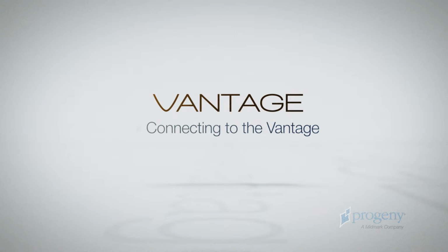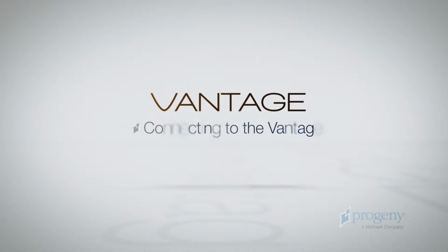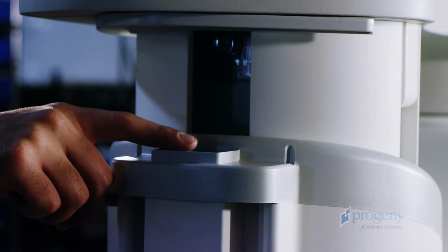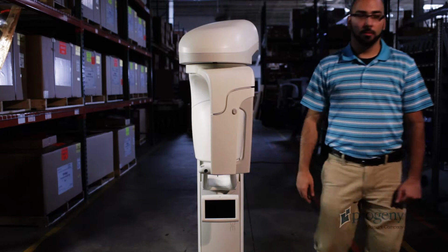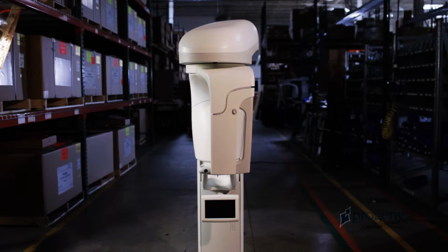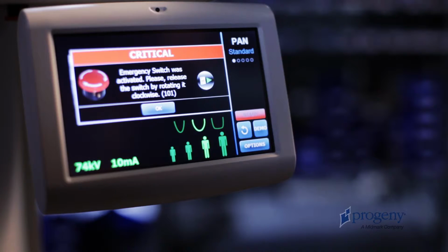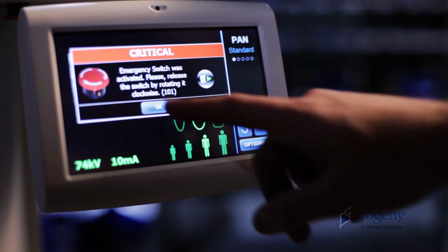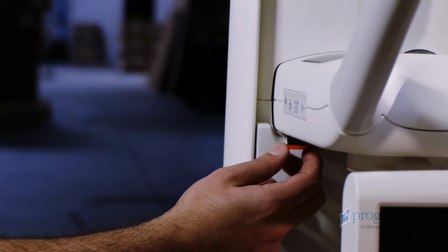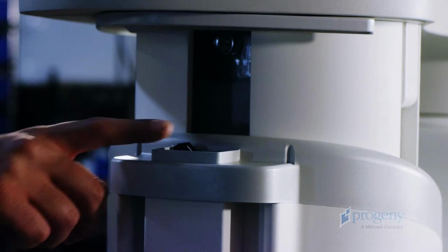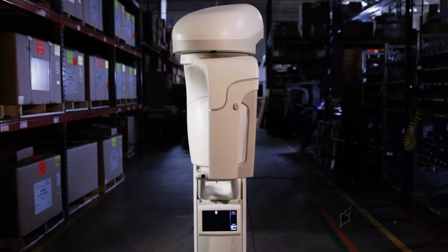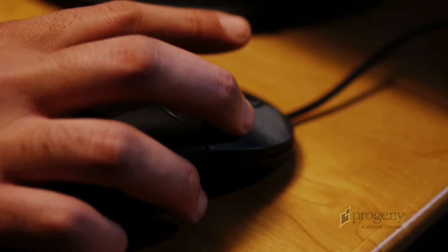Connecting your computer to the Vantage system can be set up either through Progeny Imaging image management software or through Progeny's Twain interface. Power on the Vantage by flipping the switch located at the rear of the main column. Make sure that the emergency stop switch located below the patient table has not been pressed. If so, rotate the switch to release, power cycle, and energize the Vantage again.